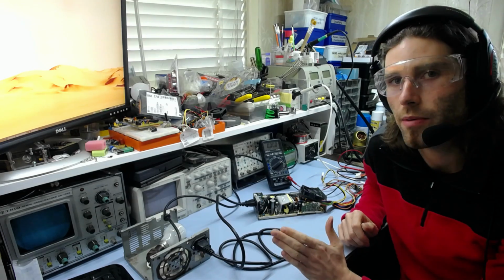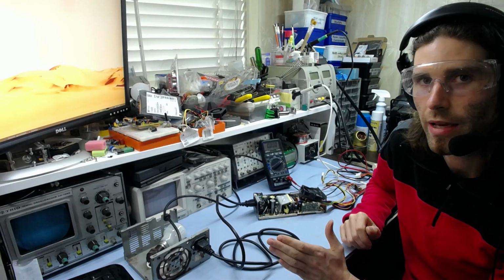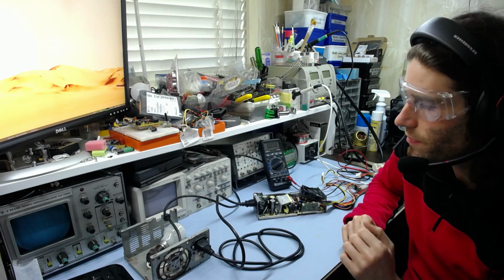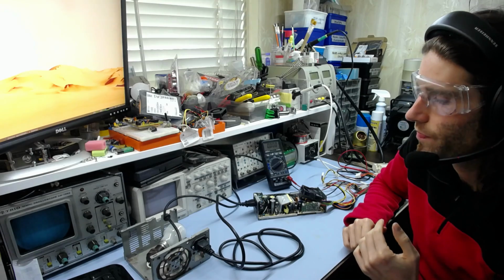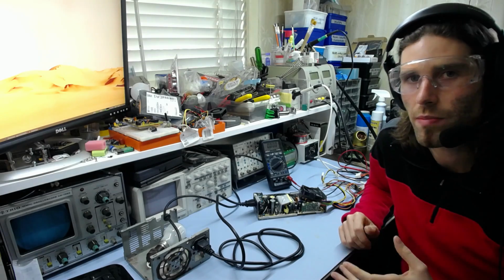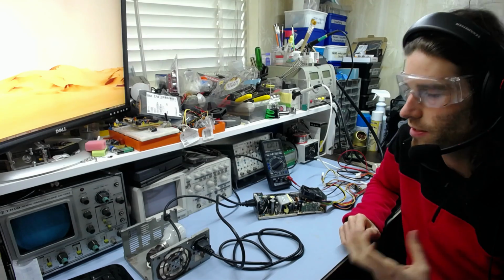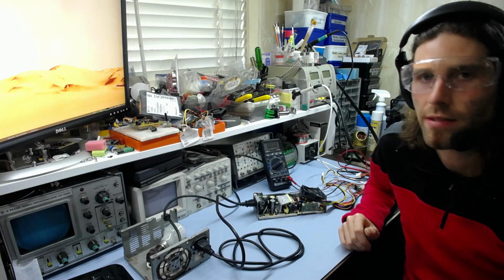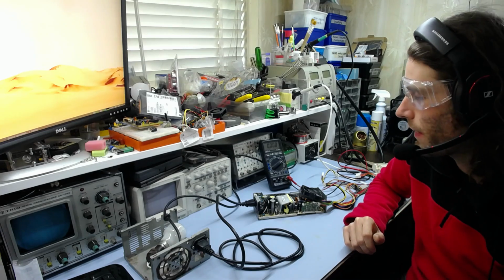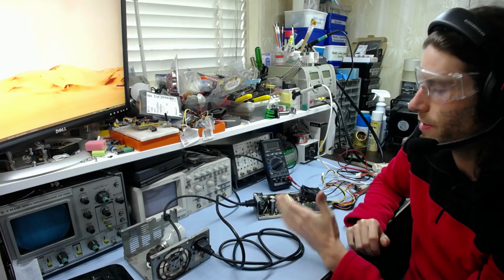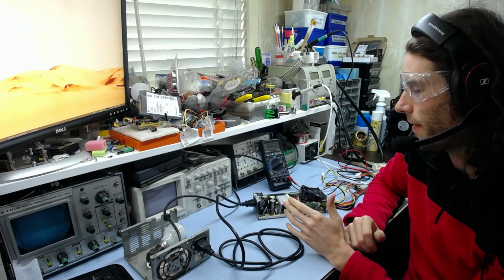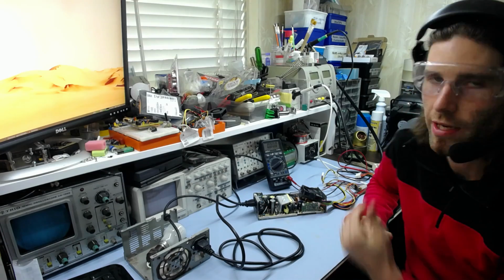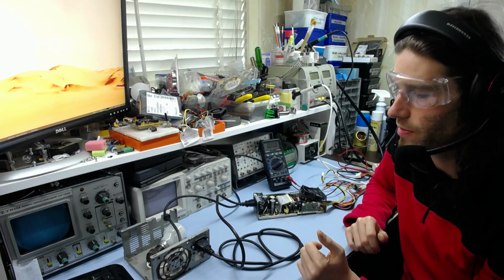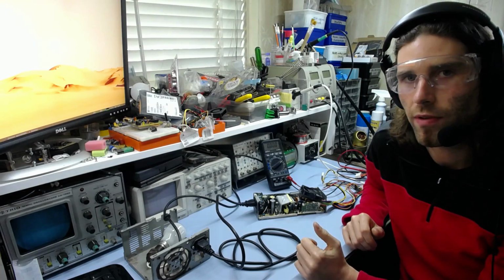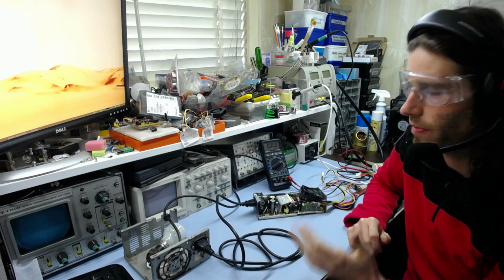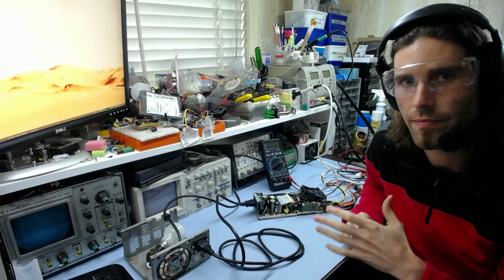The light bulb on the other hand works in the opposite way. It starts out with a low resistance, so it'll allow current through, but as it heats up, as it warms up, the resistance increases and it actually draws less current, and it prevents more current from flowing through it. So if, for example, the primary side in this was shorted, it would try to draw as much current as it could, but with the light bulb in series with it, the amount of current that can flow is limited to a maximum by whatever the light bulb normally runs at.